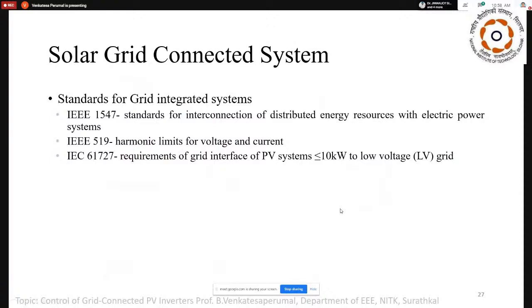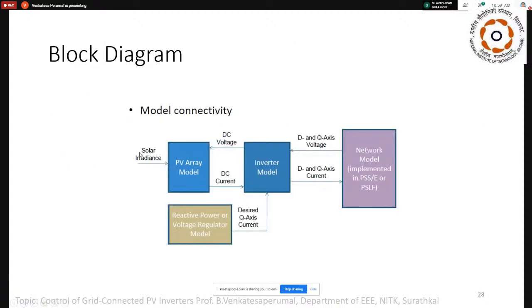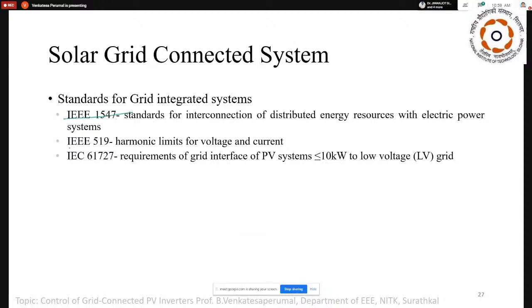Now, if I talk about that inverter, first I need to know what kind of standard it has to follow. IEEE 1547 is for distributed energy sources that we want to connect. Another IEEE standard, 519, covers harmonics and voltage and current requirements. Another IEC requirement is for grid systems less than 10 kilowatt connected to low voltage grids. We need to meet all these specifications. Only by meeting the compliance requirements of these IEEE standards can you push the power to the grid. What are all the requirements here? It is mentioned over here.